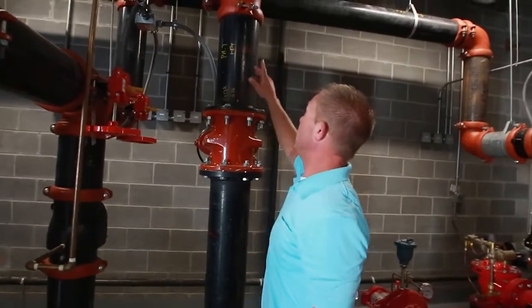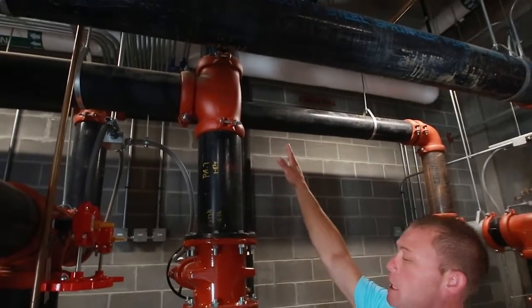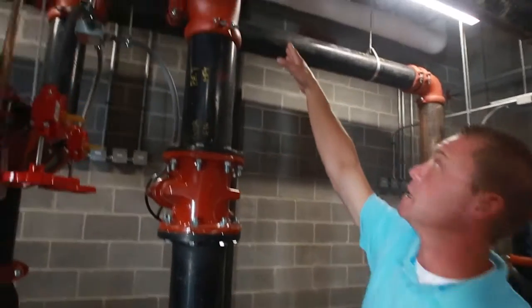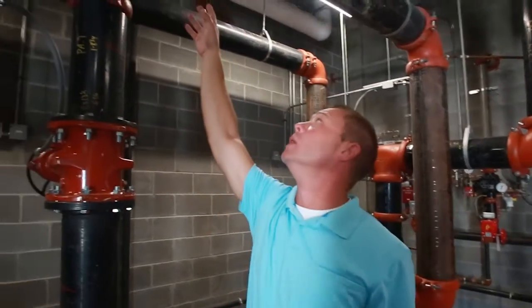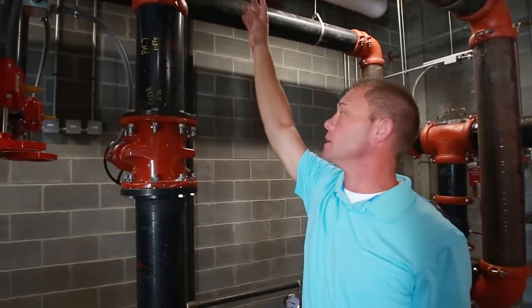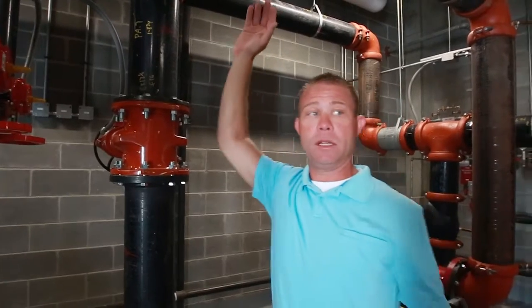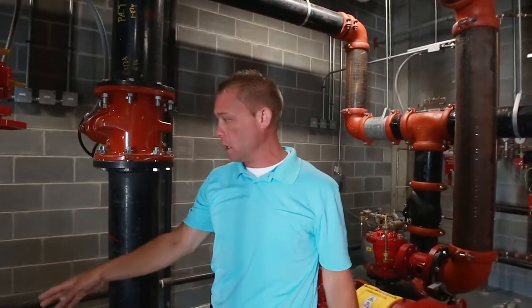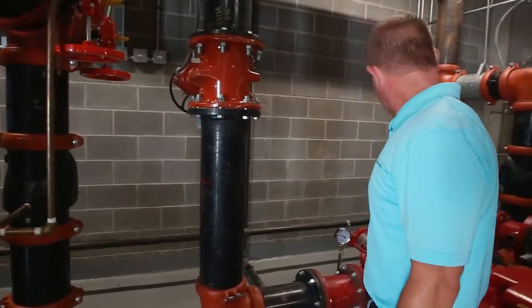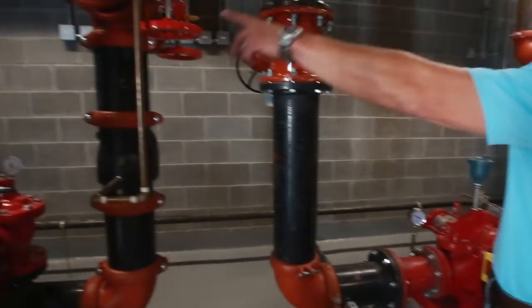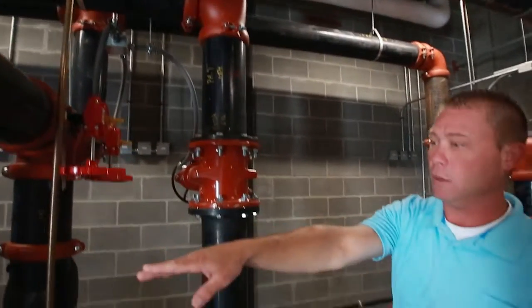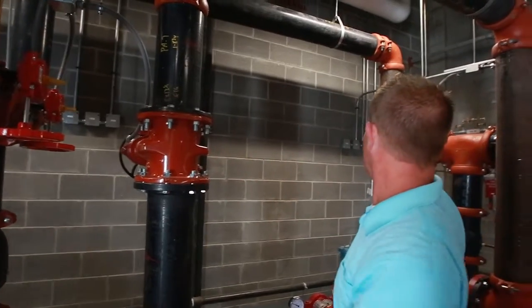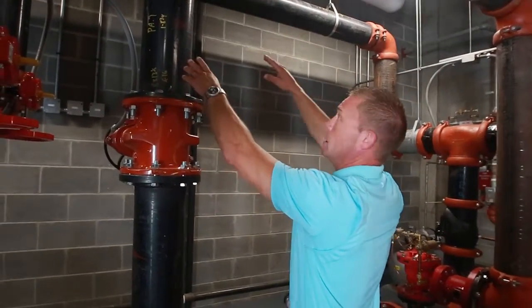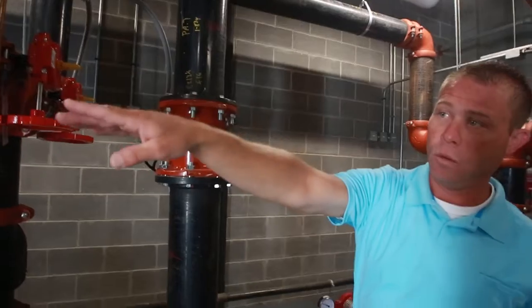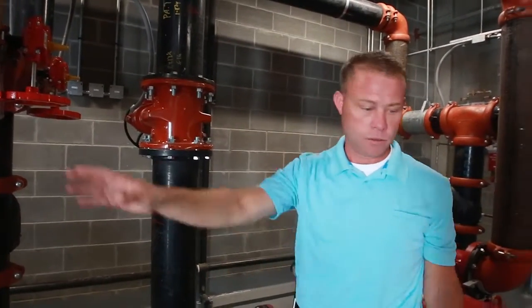We do have a bypass. That's where this T would be. In case these fire pumps were to fail, the bypass, which is the T, goes up and connects to the piping as well. It has a check valve and 2 butterflies, and that is just, like I said, to make sure you have water in case the fire pumps do go down. You have relief valves that are attached and will be piped outside, and we'll show you where that goes as well. And test headers on both of them that come up, connect, and go around, and they come out the north wall as well. And let's go take a look at those.